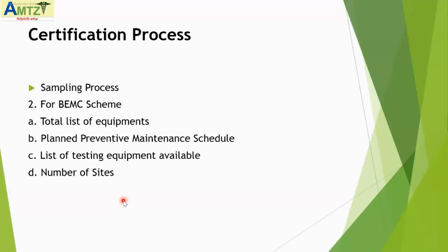And then the sampling process is very simple. As I told you, for the BEMC scheme, it depends on the equipment. What is the kind of maintenance you are doing, whether it is preventive or predictive, whatever it is, and the list of testing equipment available. Because here, if it's an active, powered device, we need certain safety test equipment, like we measure the leakage current, and we measure whether the earthing of the equipment is proper. If that is not proper, the patient could get a shock. And we look at the insulation, and certain basic test equipment would be available, or rather should be available. We look at that, we look at the number of sites, and then depending on how many sites, we decide how many to sample, depending also on which equipment is more critical. I know how to maintain a very critical equipment. I may not really go into a smaller equipment, which is not that critical. So that is one thing we see.